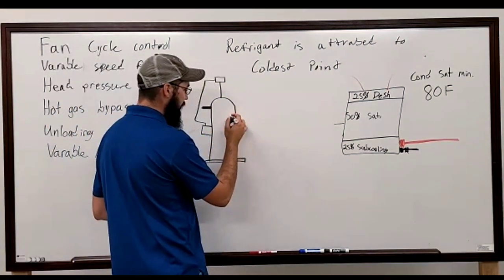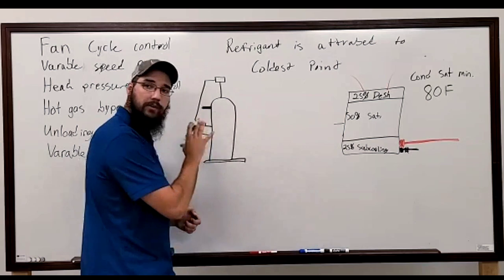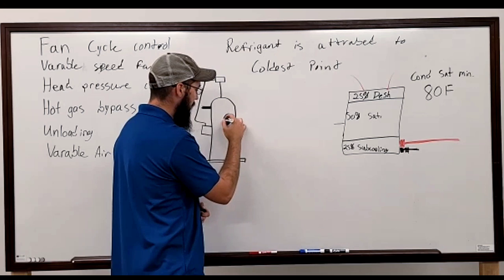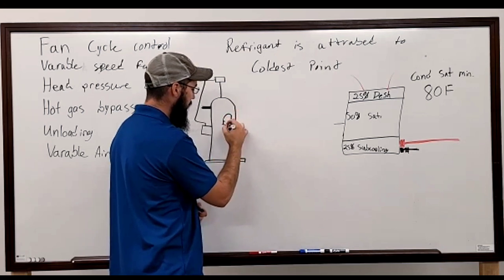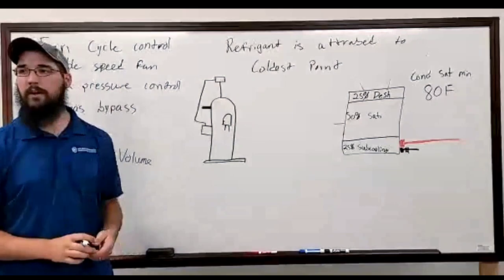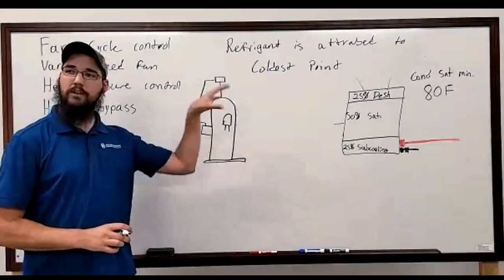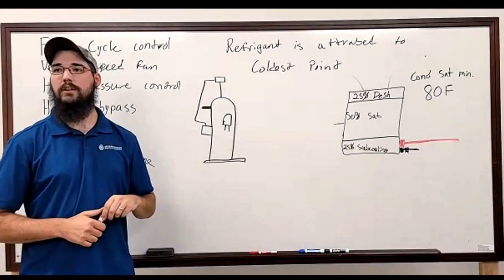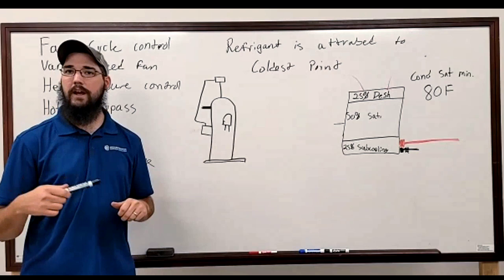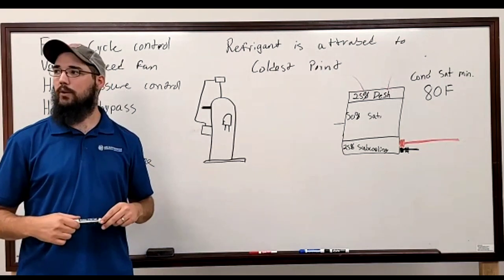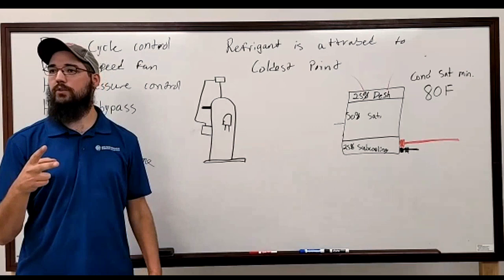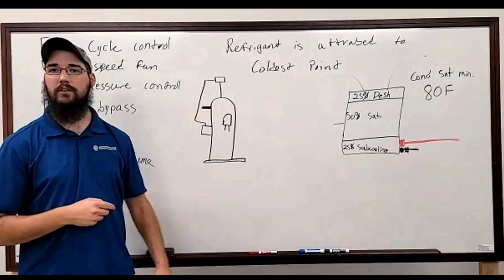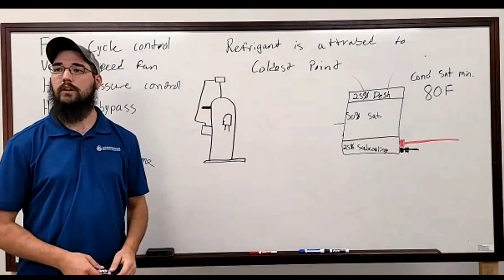And the compressors I was working on that day had internal unloaders. The only difference between that and external is you've got your main three-wire power plug, right? You'll have a separate plug with two little blue wires going through the top. So you'll have your power plug and then a second plug kind of on the back side. That is an internal electromechanical unloader. So we'll fire 24 volts on those two wires, and what's happening out here happens internally in here, just inside the compressor.